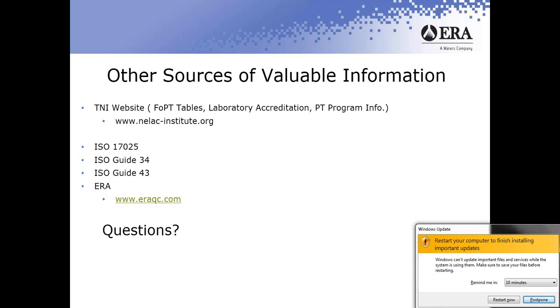Scott Frazier asks, with multi-analyte PT samples, what is the general method of selecting which analytes are present? I noticed that less stable analytes are often not present. Is there a requirement to include those at some frequency? There is a requirement that a PT provider provide not only analytes within the concentration ranges, but also that they try to cover the analyte list within a given field of proficiency testing. While it's true, and I agree there are bad actors in some mixes, PT providers still, at some point, must provide that analyte in a PT study.